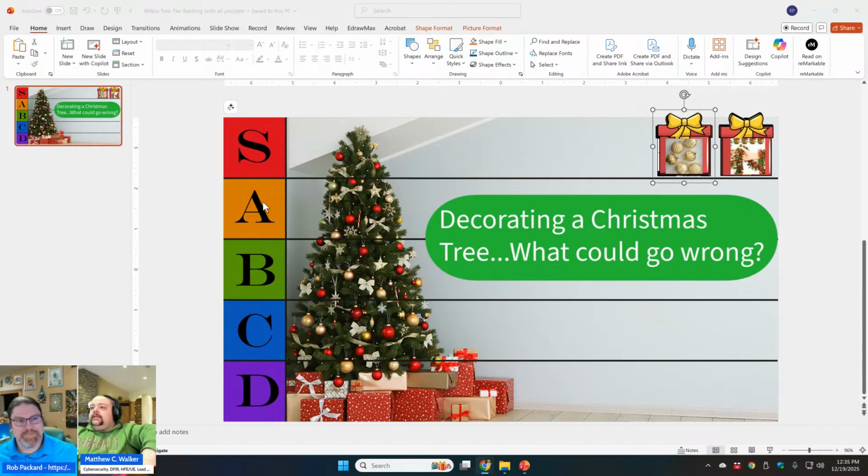If we were looking at this like a use-related risk analysis, where would we draw the line for a critical task? Right between A and B. If it requires medical attention, it's a 3 or a B, C, D. Those are the ones you have to report to the FDA, and those are the most serious. Those are also the critical tasks. Critical tasks would be something that will actually result in harm. Whereas the 1s and 2s are not something that would require reporting, and they wouldn't be considered a critical task.